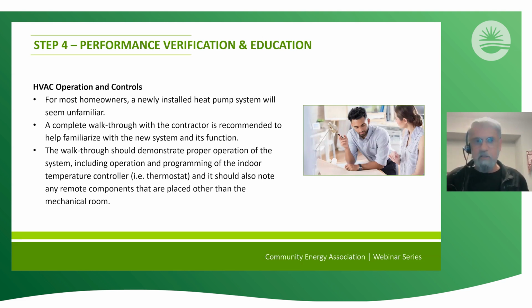Yeah, and they do it with different algorithms, time, temperature, but occasionally you may happen to be paying attention at the time when that defrost occurs. And if nobody's told you about that, that could freak you out. So it's important to let the homeowners understand that this is going to happen. It's no big deal. It's not going to interrupt your comfort level. The equipment is smart enough to know what your comfort setting is and maintain it while doing the defrost. Yep, good one.